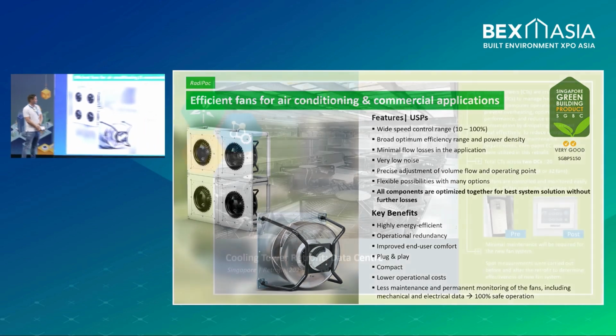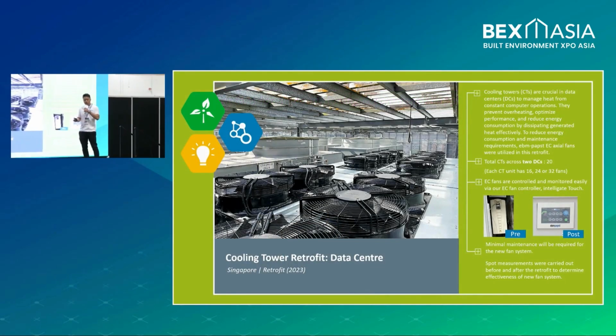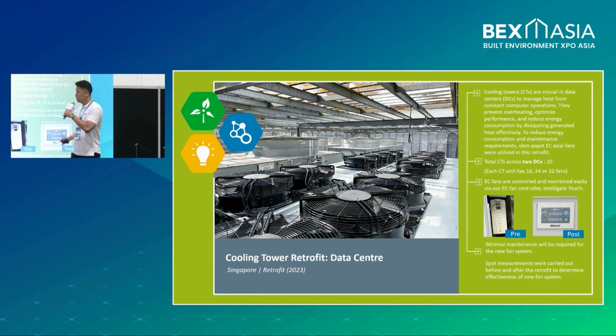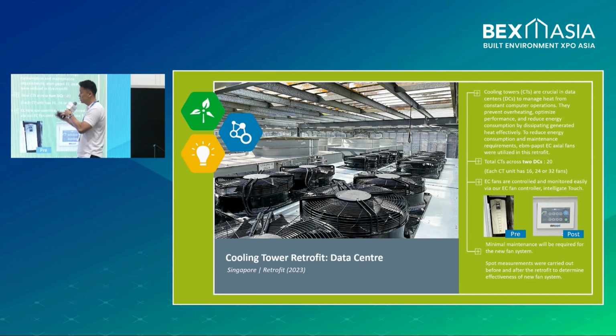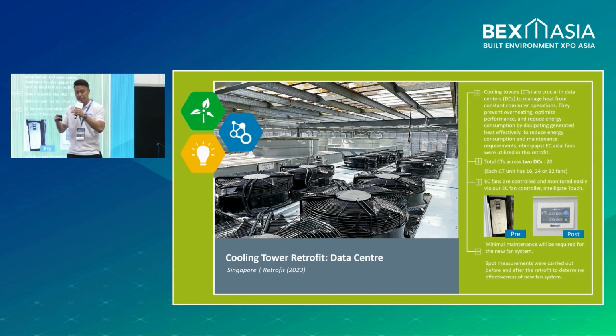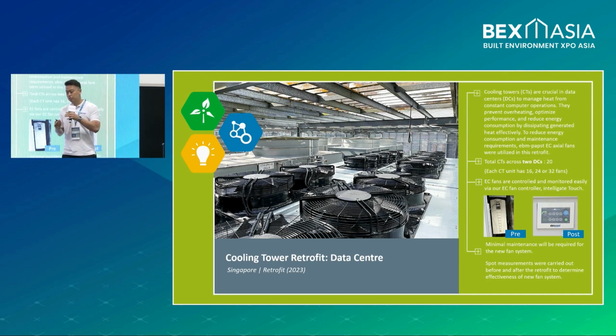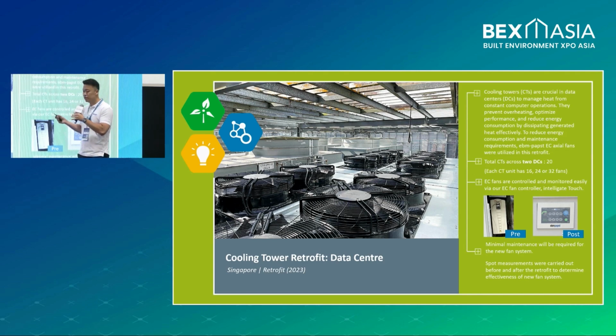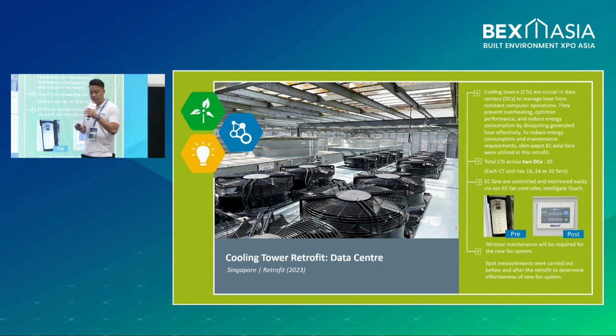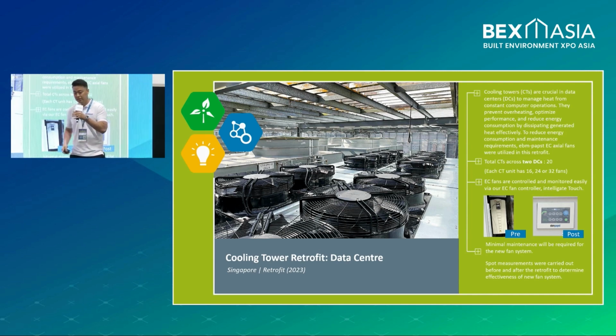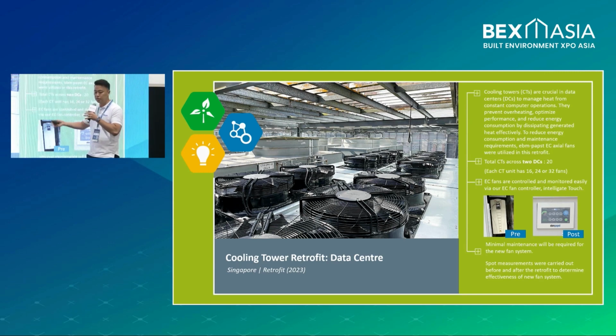Thank you, Thomas. Next, we talk about one of the cooling tower retrofits in one of the data centers in Singapore. For your info, we are converting a counterflow tower single fan to our multiple-fan EC fan solution, from 1 fan to 8, up to a maximum of 16 per cell. In cooling towers, most of the headache is maintenance and breakdown issues. One good thing about EC fans is there's no need for maintenance, and the lifespan can last 100,000 hours, which is close to 10 years. There's no need for greasing or belt changes because it's direct driven.